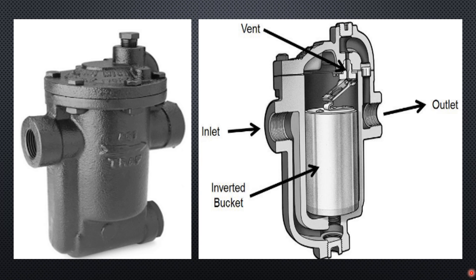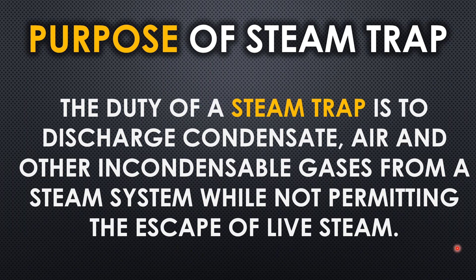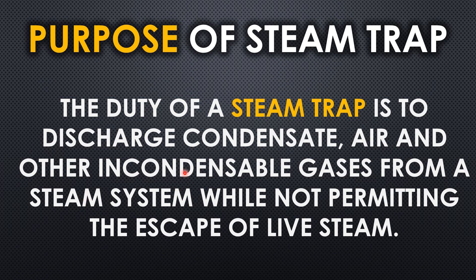This is what a steam trap looks like — it has an inlet and an outlet. The condensate from the steam header goes into the steam trap, and when the trap is filled with condensate, it allows the condensate to pass through. The purpose of the steam trap is to discharge condensate, air, and other non-condensable gases from the steam system while not permitting the escape of live steam. It allows condensate to drain but prevents steam from passing through.